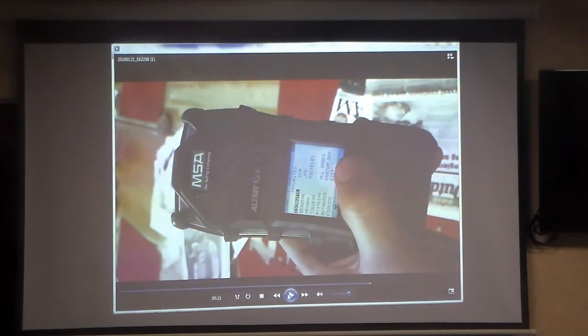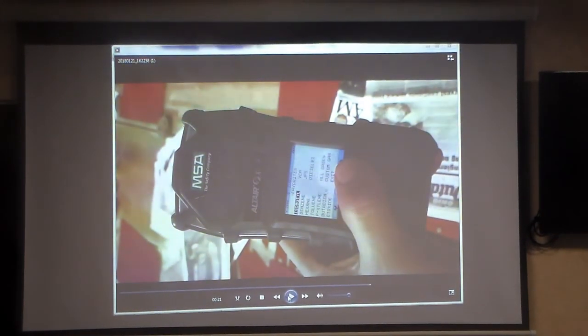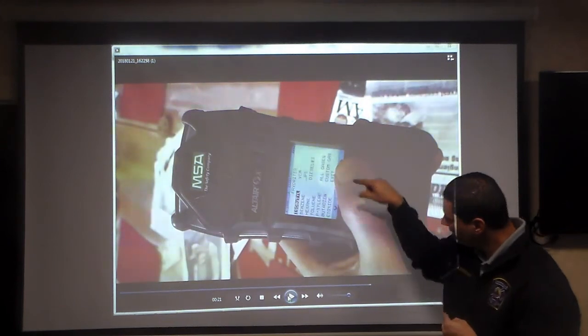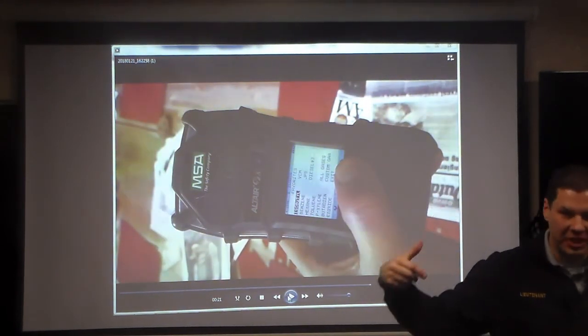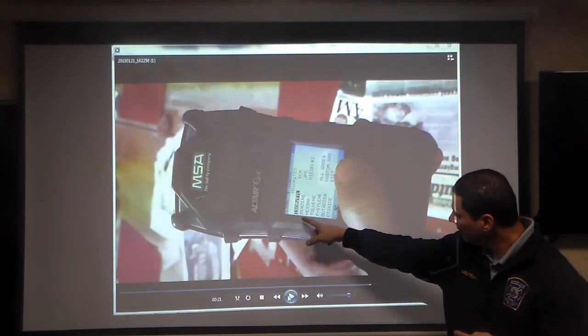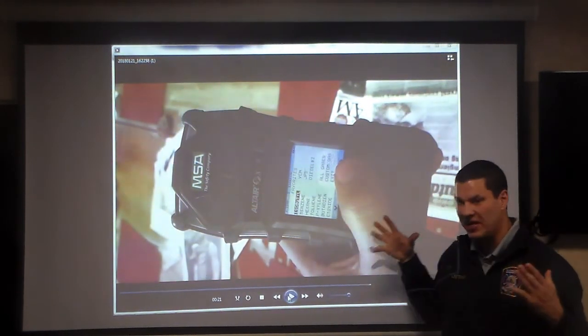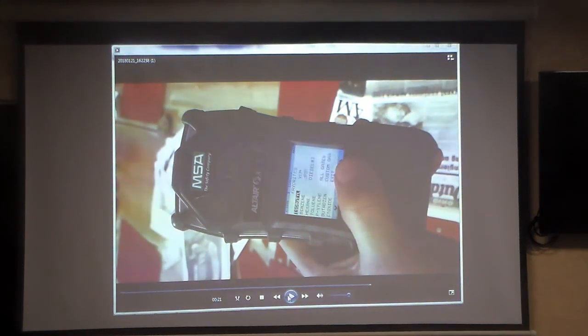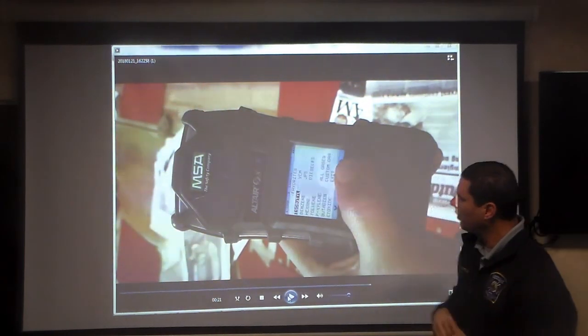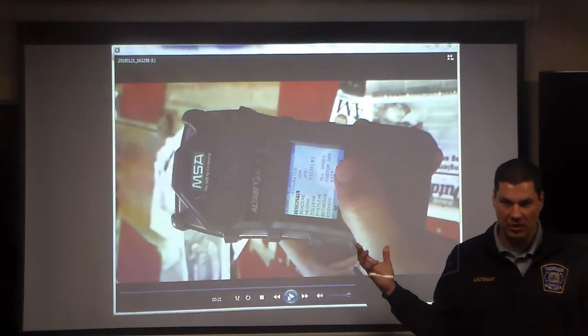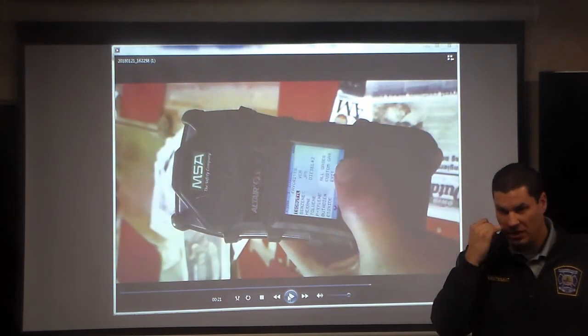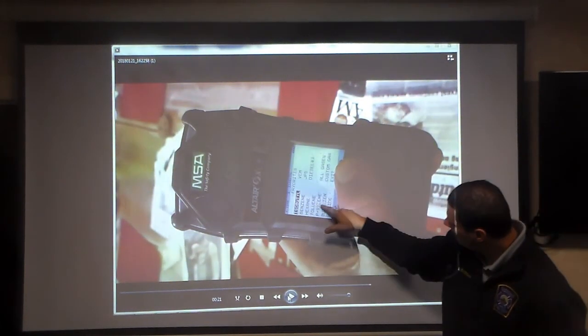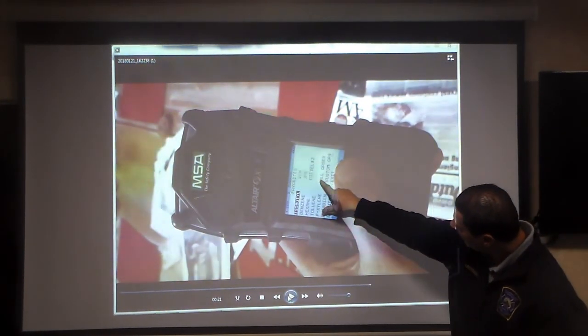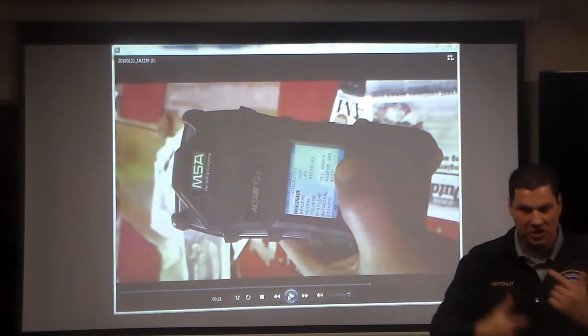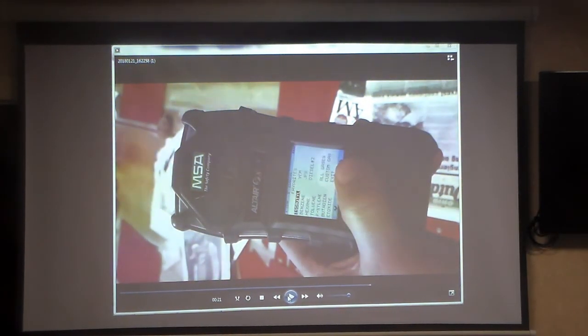So you understand how this works. You know the name of the gas, that's important. You cycle using that button until you get to the page that says change VOC gas. Right there are the top 10 favorites, the default favorites. If it's one of these, you just click it, click yes, accept, and you're metering for that gas. If it's not in the favorites list, go to all gases and cycle through until you find the one you're looking for.